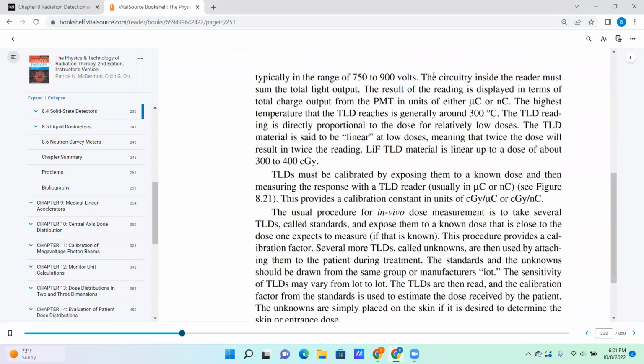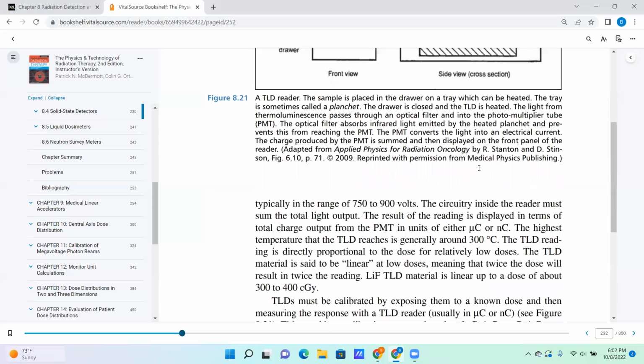typically within 750 to 900 volts. The circuitry inside the reader must sum the total light output. The result of the reading is displayed in terms of the total charge output from the PMT in units of either microcoulombs or nanocoulombs. The highest temperature that the TLD reaches is generally around 300 centigrade. TLD reading is directly proportional to the dose for relatively low doses. The TLD material is said to be linear at low doses, meaning that twice the dose will result in twice the reading.